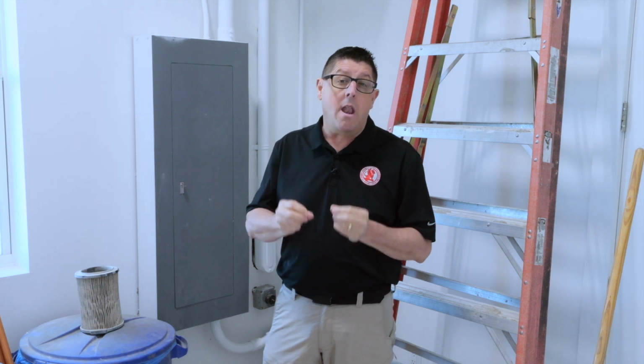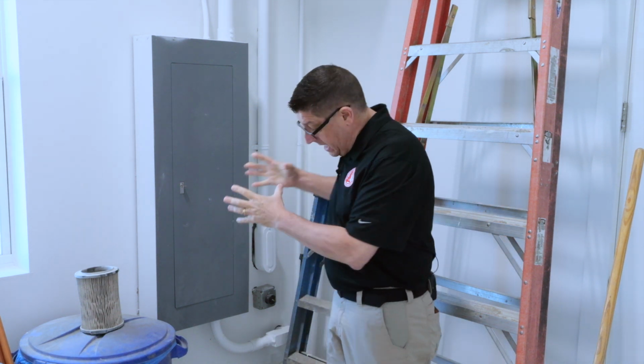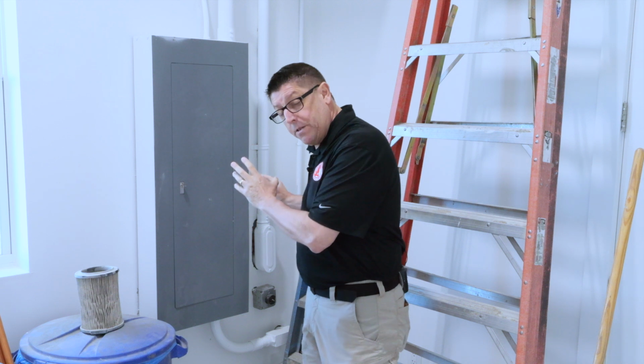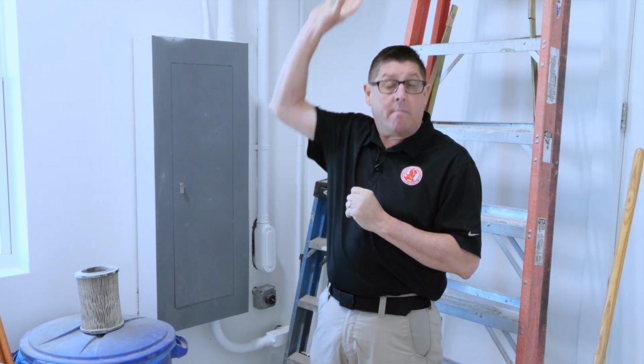Now, transformers are not required to have the same working space rules as the rest of the electric does. So what I mean is the 30, 36, 78 rule does not apply, but all transformers have to be accessible for servicing. So that's why some transformers, to eliminate the need for the space on the floor, are mounted up high, as in this case.